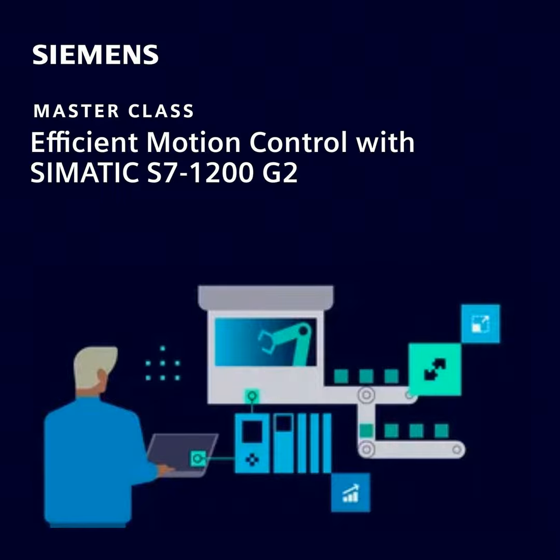To simplify the implementation of motion control functions, SIMATIC S7-1200 G2 supports a wide range of technology objects. Technology objects are software objects that realize the whole motion control functionality of your application. For example, it automatically calculates the path needed for an accurate positioning movement and transforms the speed set point into a format the servo drive can use. Technology objects represent mechanical components and encapsulate the technological functionality needed for that component.